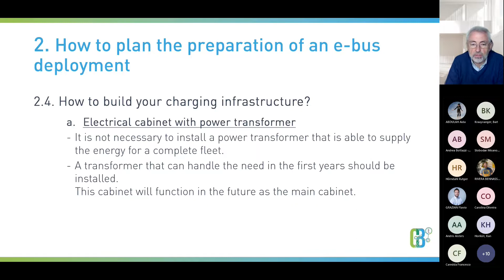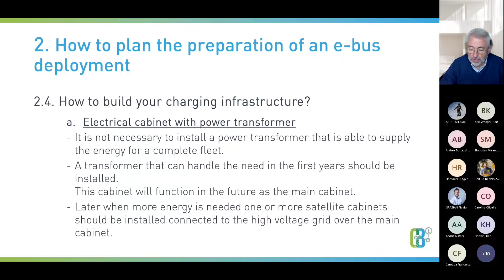Later, when more energy is needed, one or more satellite cabinets should be installed, connected to the high voltage grid over the main cabinet. Normally the size of a cabinet depends on the size of the transformer, but here you must also account for the high voltage connections to future satellite cabinets. Space must be foreseen to accommodate the departure modules you'll install later, otherwise you'll have to change your cabinet again, and that's not an easy thing to do.